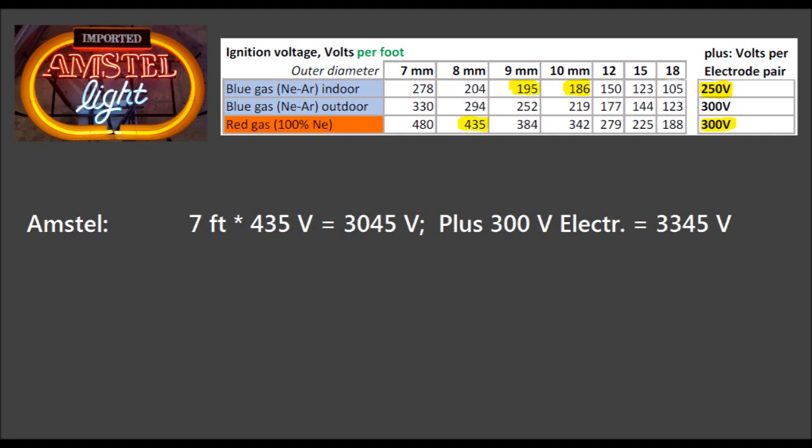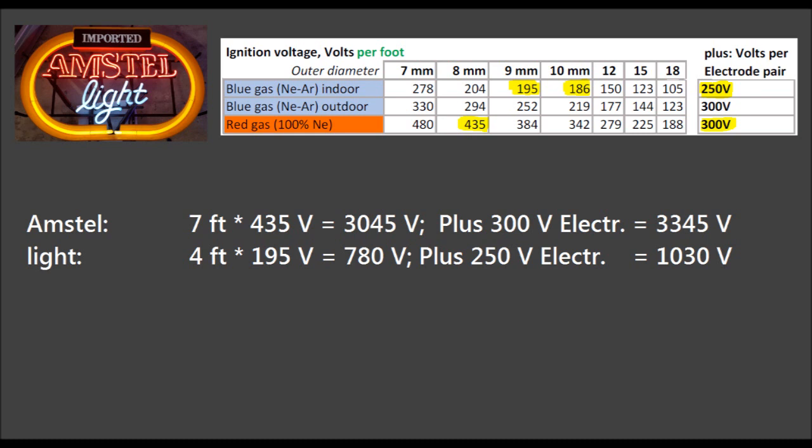For the Amstel tube, we take the measured length of seven feet times 435 volts per foot, which gives us the voltage requirement of the tube, plus 300 volts for the electrode pair on red gas, totaling 3,345 volts. For the 'light' tube, calculating with nine millimeters at four feet long, we get 780 volts voltage drop plus 250 for the electrodes — blue gas indoor — giving us 1,030 volts.